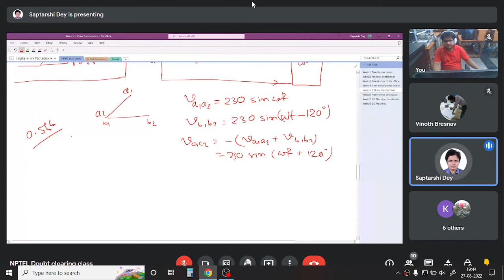Since the secondary side is still receiving a balanced supply, we can connect a three-phase balanced load to it. The three-phase balanced load will see a three-phase balanced supply voltage, and it will draw a three-phase balanced current from it. So from the load point of view, nothing will change. The only thing is that it cannot deliver the full load. It will deliver the load at a lower level. If you see the lecture, the level is 0.566, something close to this, of the actual load. So if the actual transformer could supply say 1 kVA, now it can supply 0.566 kVA if this open delta connection happens.